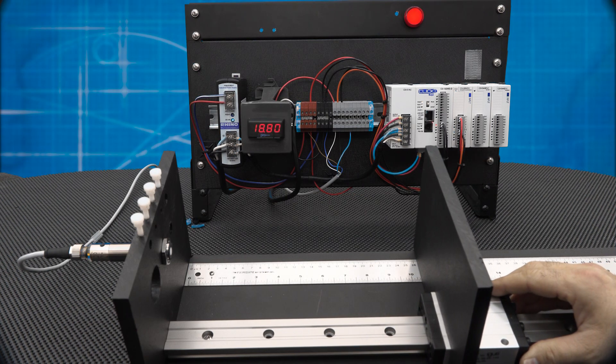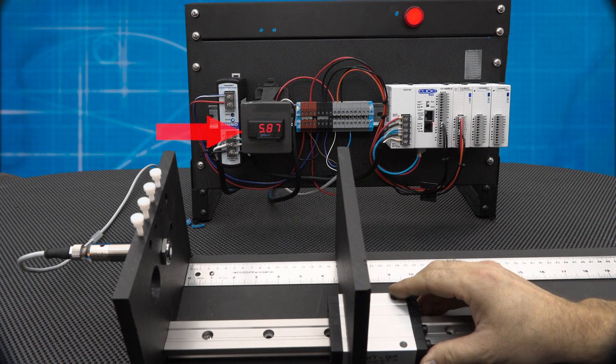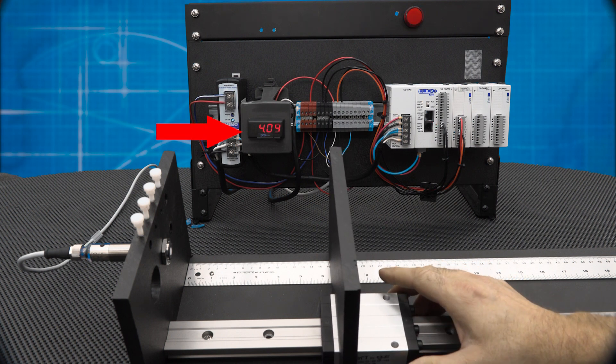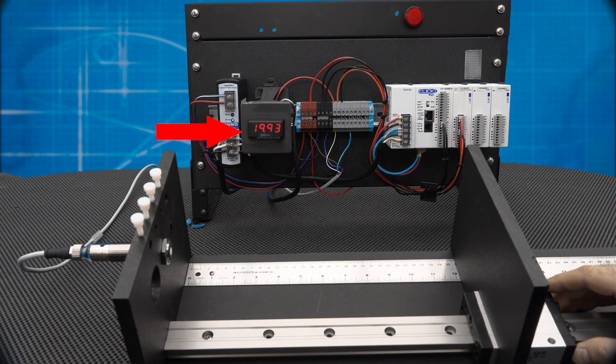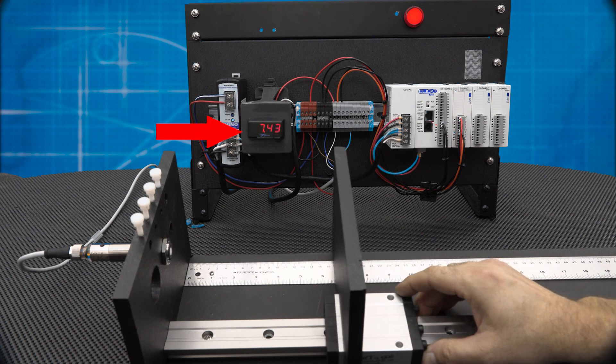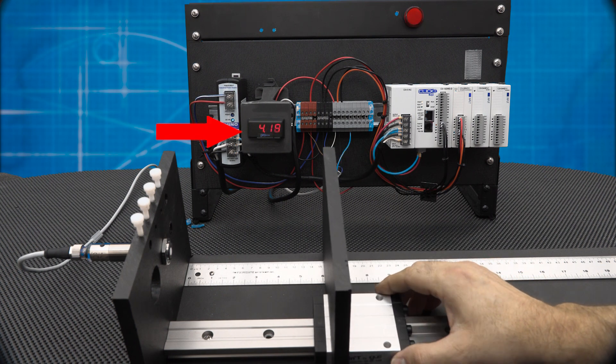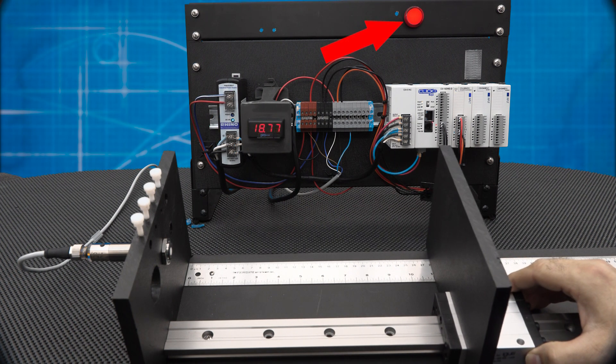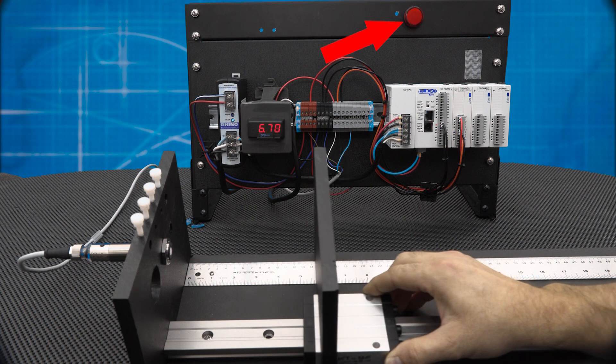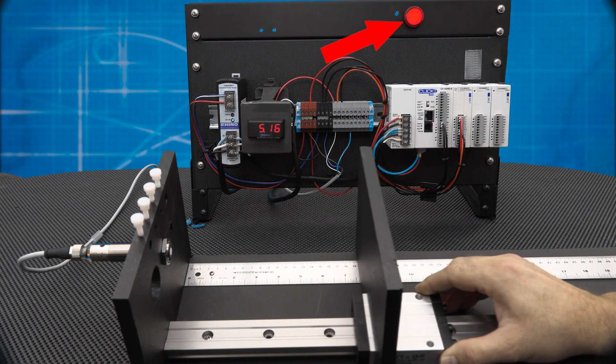When I slide the target back and forth, the analog output ramps up from 4 to 20, with 4 being at the closest target and 20 being at the furthest target. The digital output is on from 4 to 11 inches and turns off when we pass either of those limits.